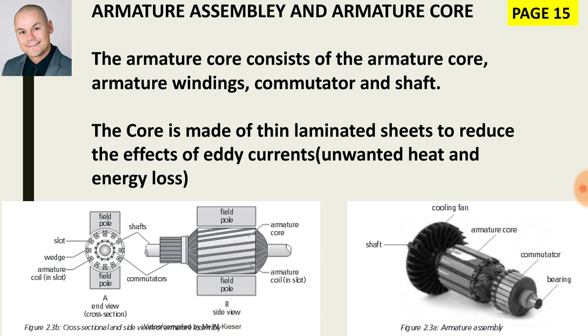The armature assembly consists of the armature core, armature windings, commutator, shaft, bearings, and cooling fan. The armature core itself is made up of thin slices of laminated steel sheets to reduce the effects of eddy currents. The negative consequences of eddy currents are unwanted heat and energy loss.